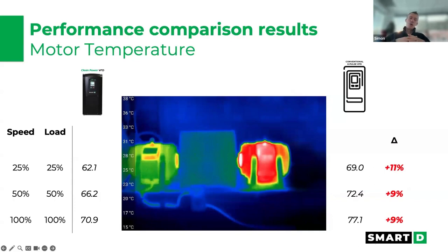And ironically, we deploy drives to preserve motors so that they don't get the high current peak when you start your motor from a contactor. But at the same time, you're inducing other problems that are actually reducing their lifespan. And temperature is certainly one of the key elements here. By having a higher running temperature, you're actually reducing the lifespan of the motor. And so by going with a clean power VFD, you're going back to the intended original lifespan for the motor.